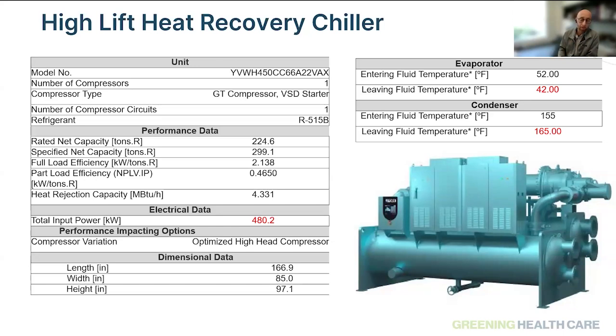And for this type of application, for heat recovery chillers, no, these have been around for a long time, and the technology exists. But as refrigerant policy changes have been affecting the entire industry, we shifted our compressor designs to serve that requirement, while also recognizing the market out there of existing facilities that don't have the budget to replace their entire hot water hydronic system but want to utilize the existing simultaneous heating and cooling load within their facility. So that's where this came from.